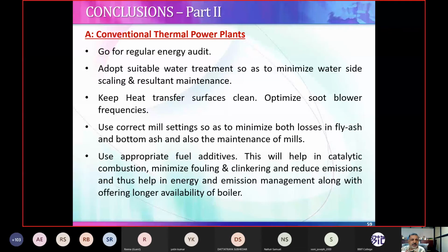Third aspect: keep heat transfer surfaces clean, optimize soot blower frequencies. Normally in large boilers there are soot blowers which blow steam over the surfaces so that all the soot is removed and the surface becomes clean. So minimize or optimize these soot blower frequencies first.